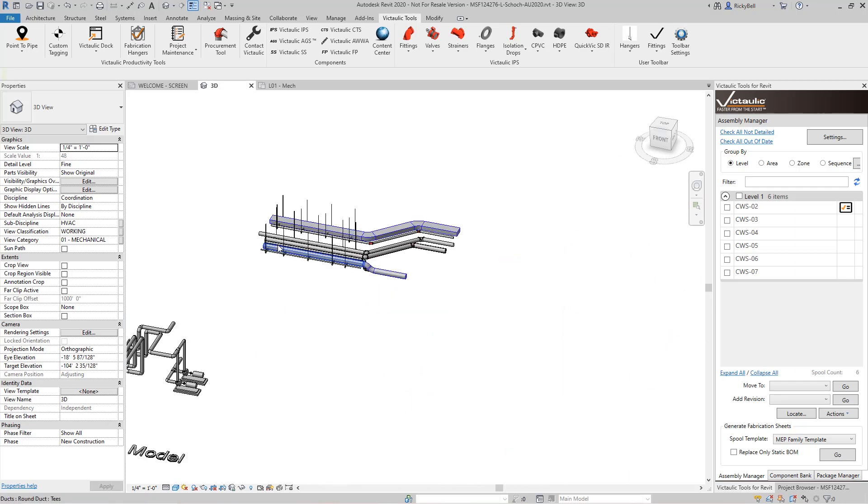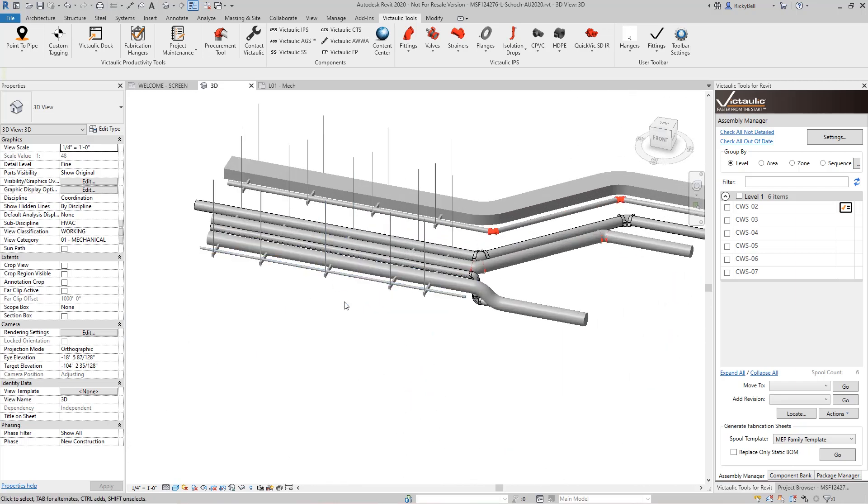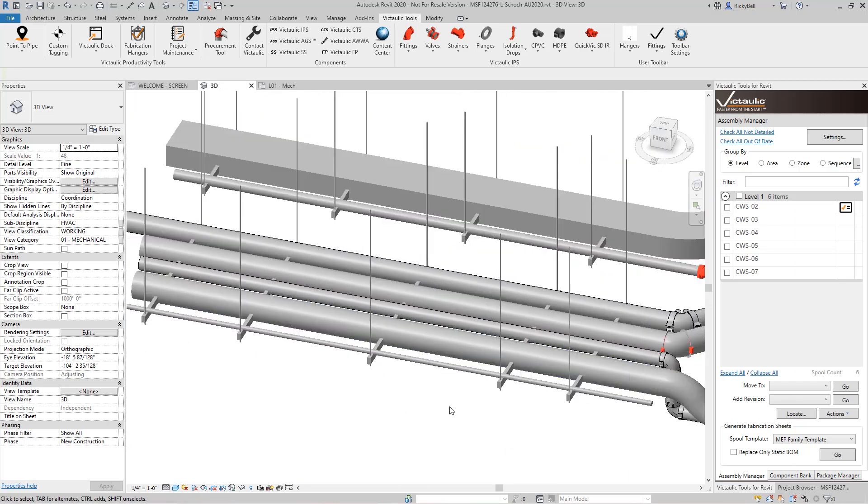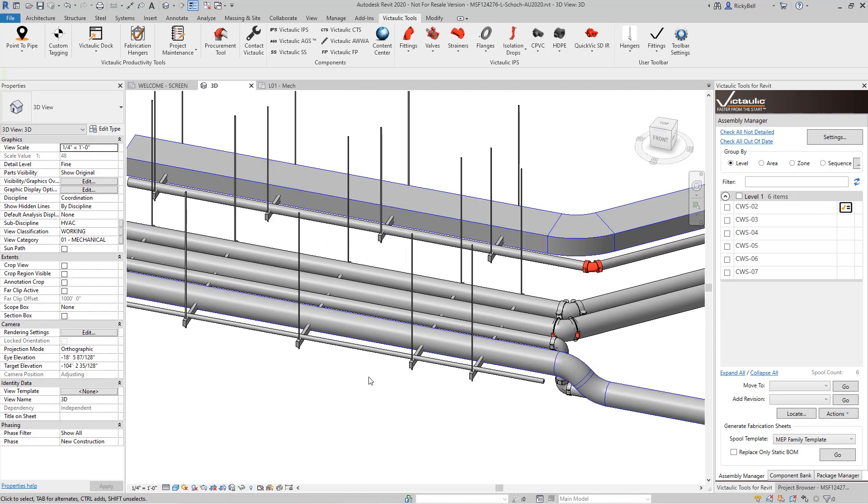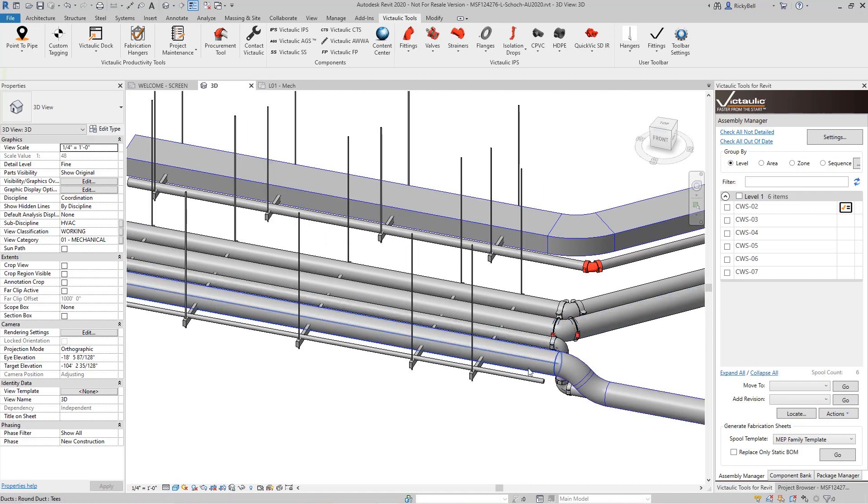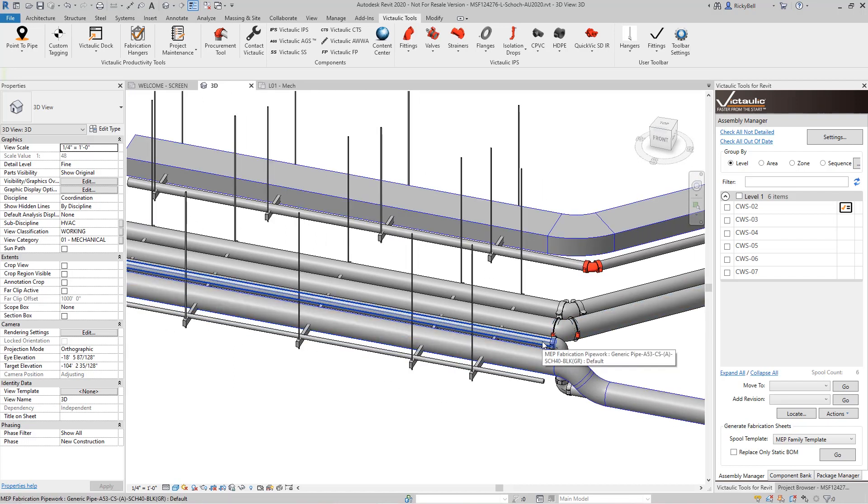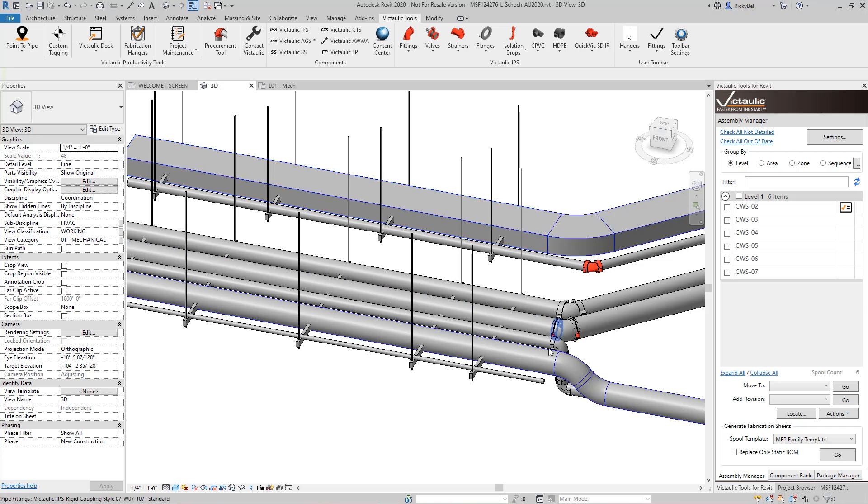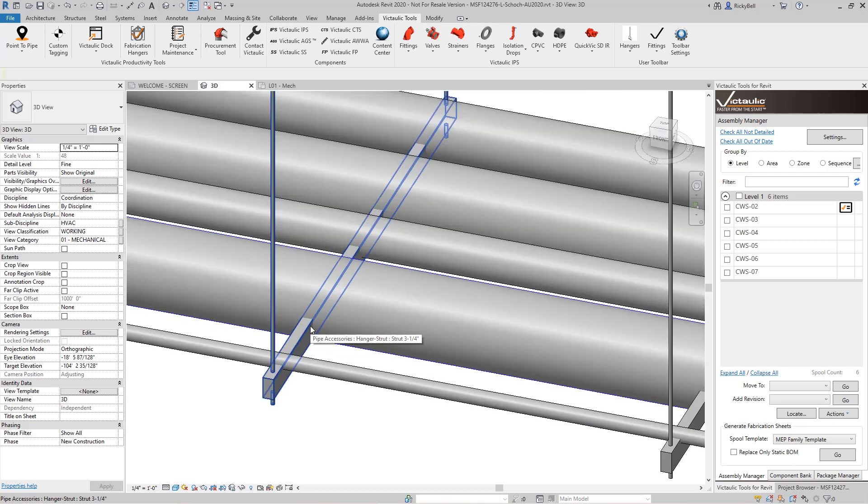We'll go over here to this section of the model where I have a few hangers set up and I have multiple trades going on. I've got duct and conduit and fabrication parts with insulation on them. I've got pipe with insulation on it. I've got some square duct up here, some rounds down here. It's a whole mix of things that you could put side by side on a hanger. And I'm sure this situation is all too familiar where you set the center line of your hanger to match the center line of your pipe and you end up with a clash right in the middle of your model like this.